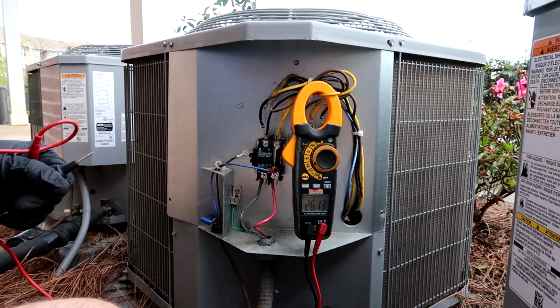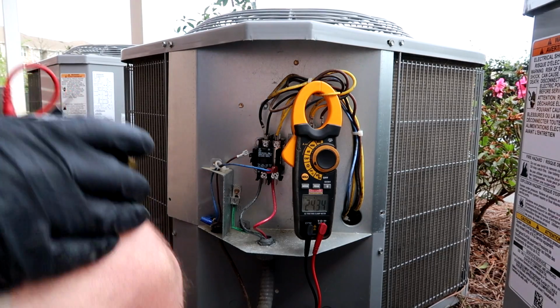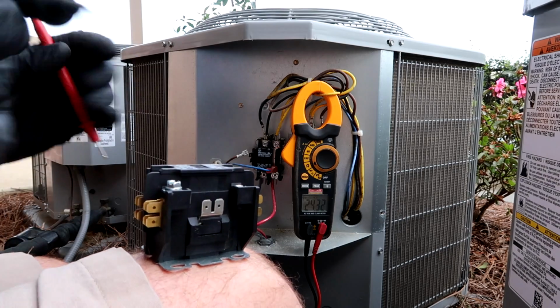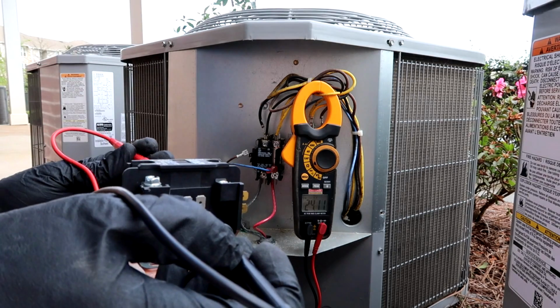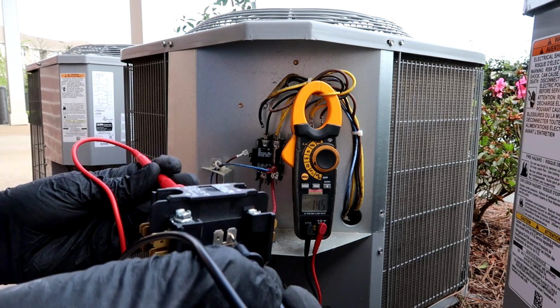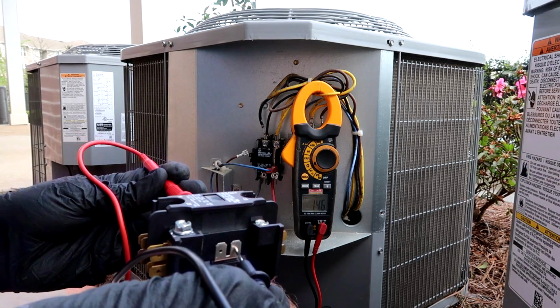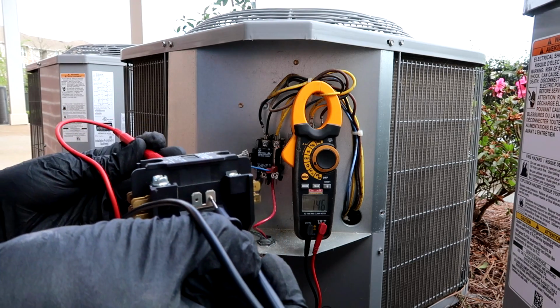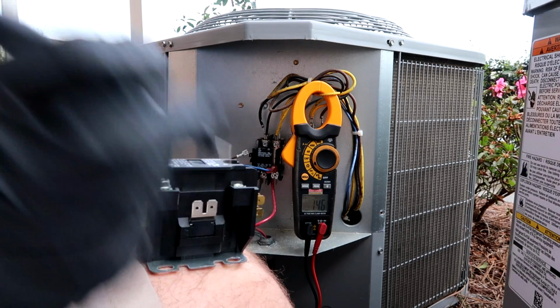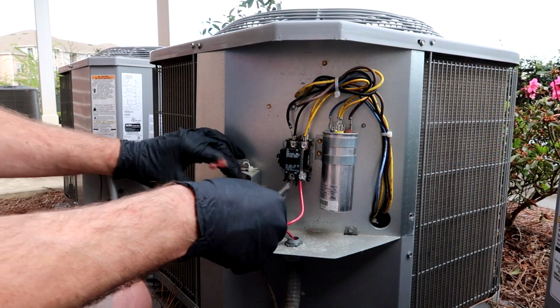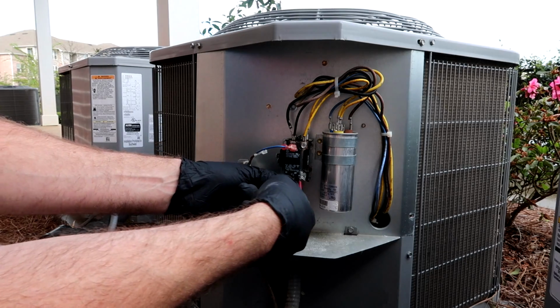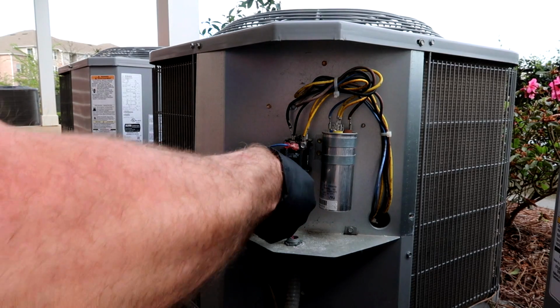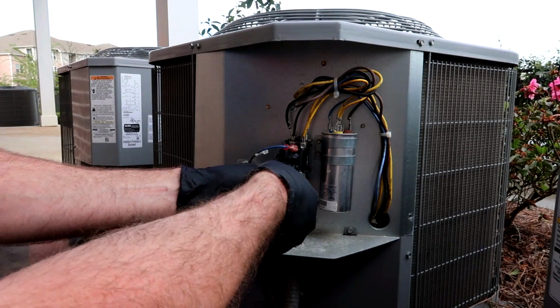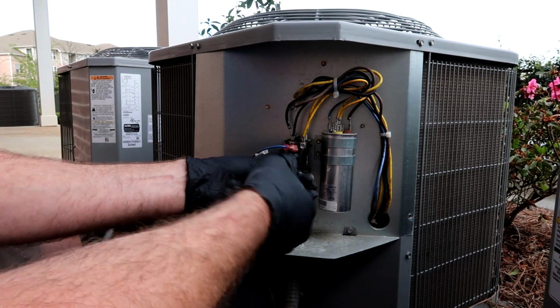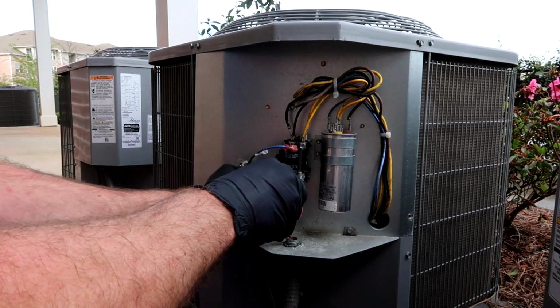I brought a new one. Let's do a good one. So a good one should read 14.6. So that's how I know this is a bad contactor. Alright, it's not hard to change out a contactor. Power is off, by the way. I want to make sure the power's off. I just don't know why it didn't pop the fuse. Might have to change that transformer out too, because it was smelling cooked.